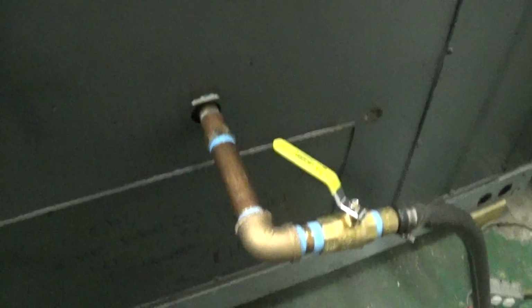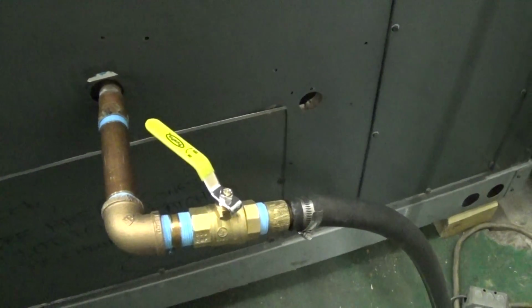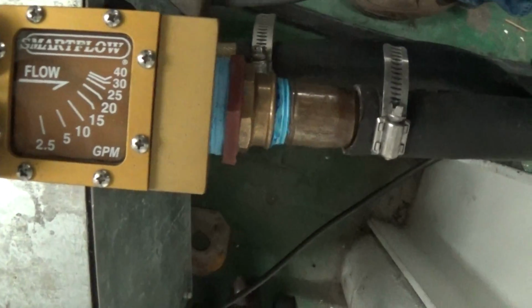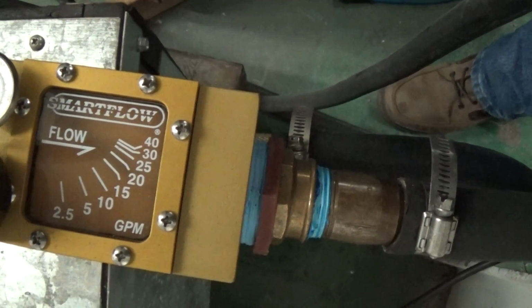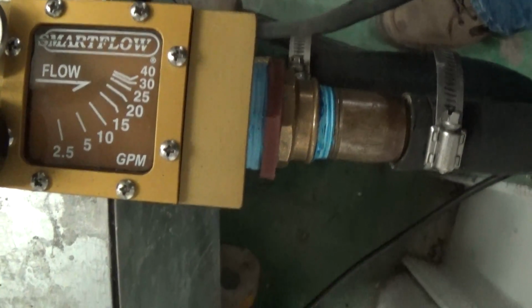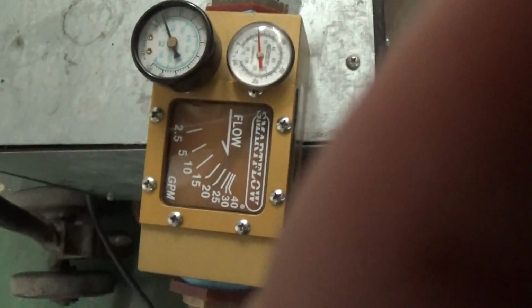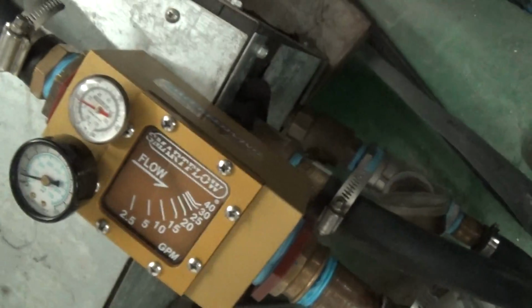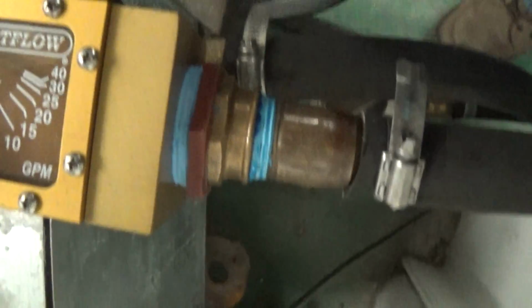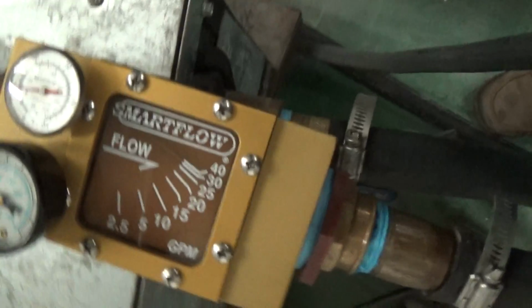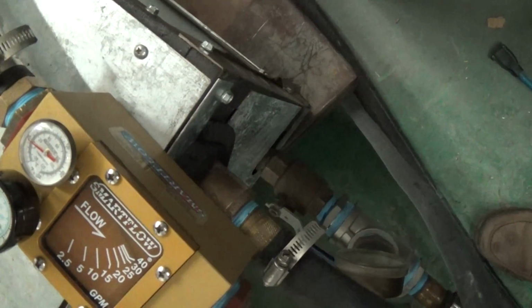Your fluid connections are on the outside here, and we put a shut-off in our little test circuit. We're not running the air handler right now, but we do put in a flow meter. You can see we probably have it adjusted at 20 GPM, maybe a little bit less. This pump's capable of more. If I open the shut-off more, now you can see we're up to 30 or 40. But I'm going to bring it back down into what I think is a more reasonable range, back down to the 20 GPM area.